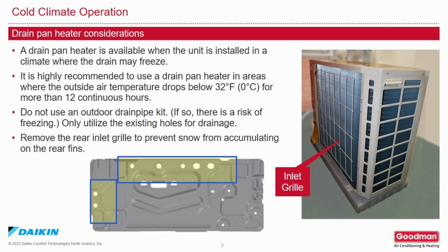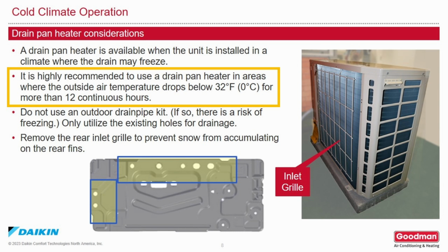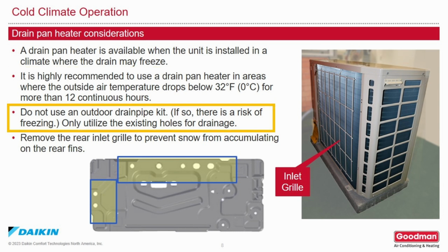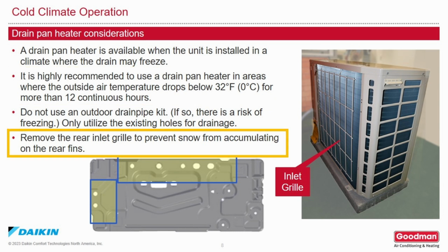When installing a unit in a cold climate location, it is highly recommended that you use a drain pan heater in areas where the outside temperature gets below 32 degrees Fahrenheit for 12 or more continuous hours to prevent damage to the outdoor coil. Do not use an outdoor drain pipe kit, and remove the rear inlet grill to prevent snow from accumulating on the rear fins.